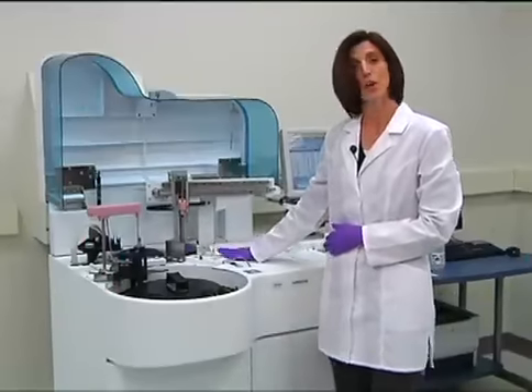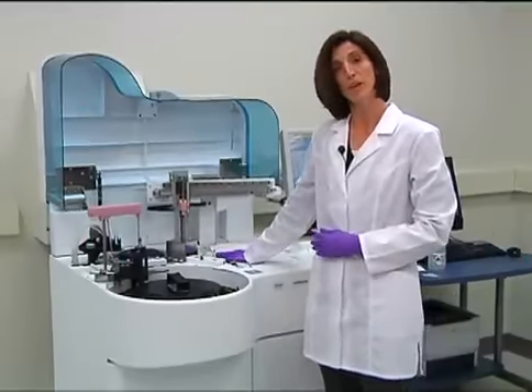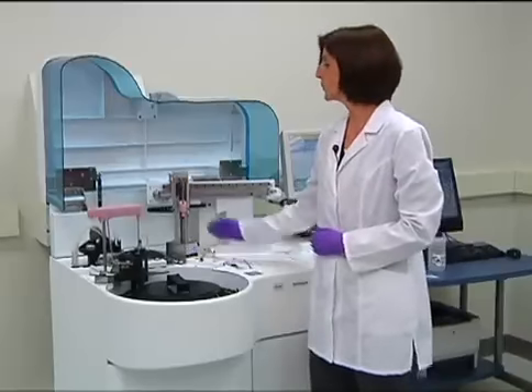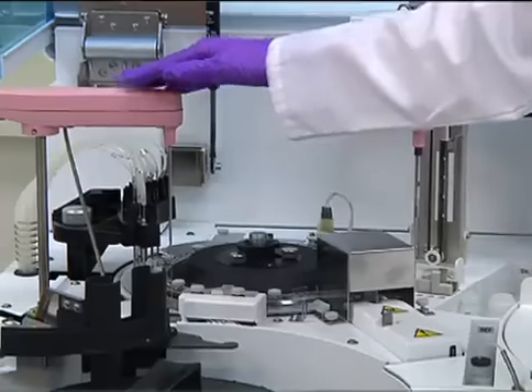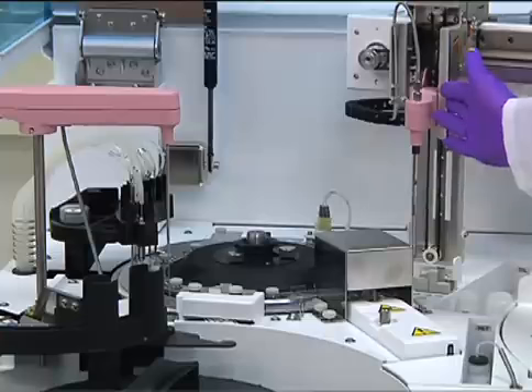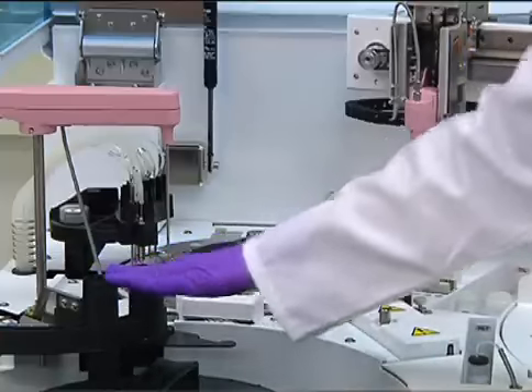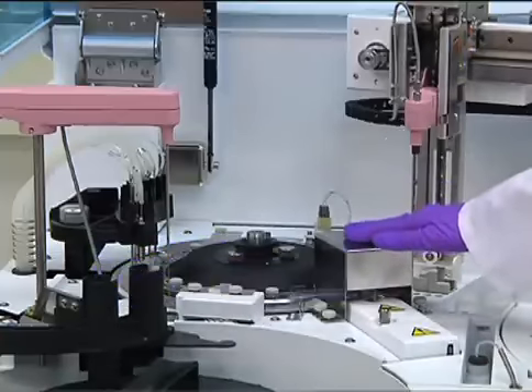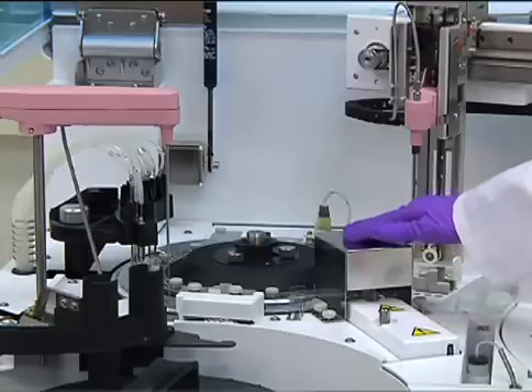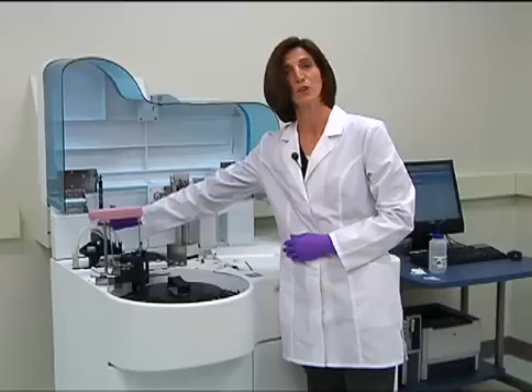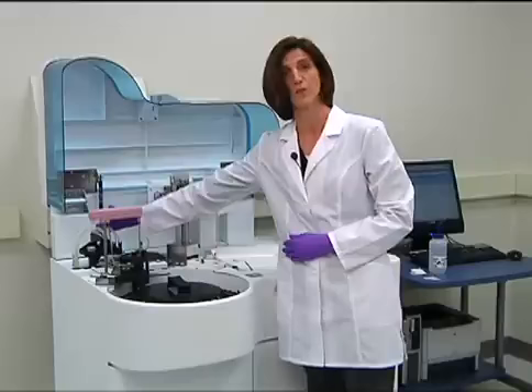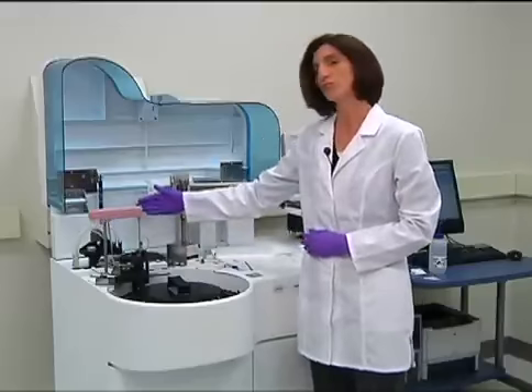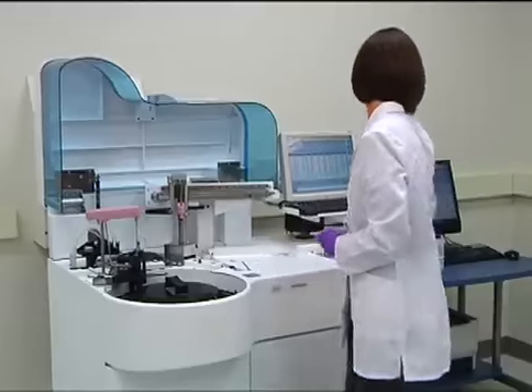Once we have completed our reagent inventory, we're ready to perform the hands-on maintenance. So what we will be cleaning will be the sample probe, the reagent probe, the sample shield pipe, and the sipper nozzle, which is underneath the cover. We will also be cleaning the cell rinse unit, which is located to the side of the analyzer. So what we will be using to clean the probes, shield pipe, and nozzle will be an alcohol pad.